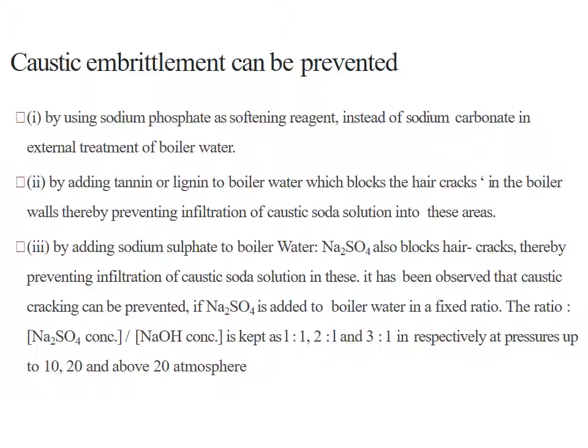It has been observed that caustic cracking can be prevented if sodium sulfate is added to boiler water in the ratio of 1:1, 2:1 and 3:1 respectively at pressures up to 10, 20 and above 20 atmospheres. Here is the assignment: What is boiler corrosion, and describe various boiler corrosion causing agents.